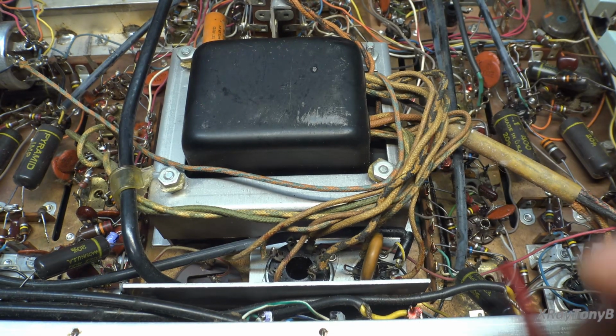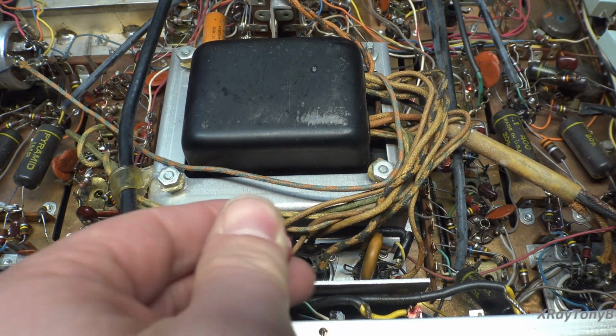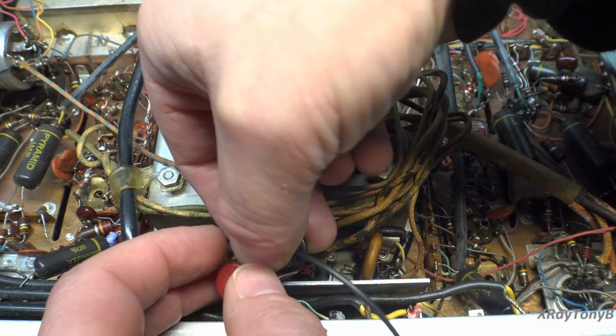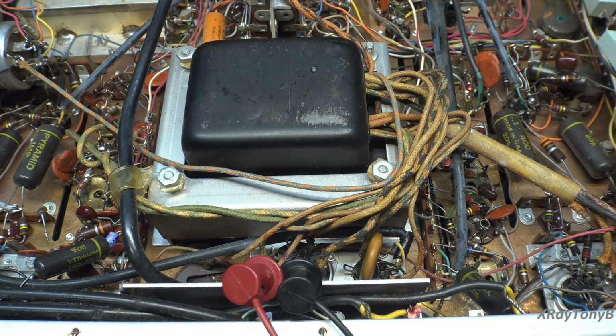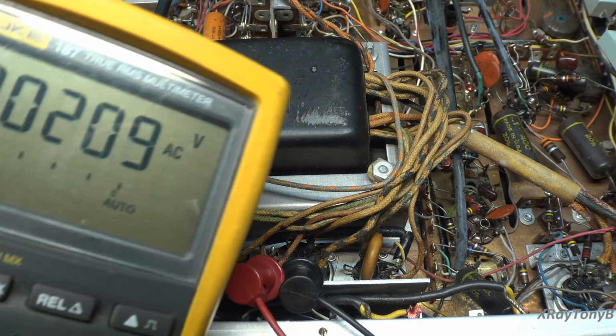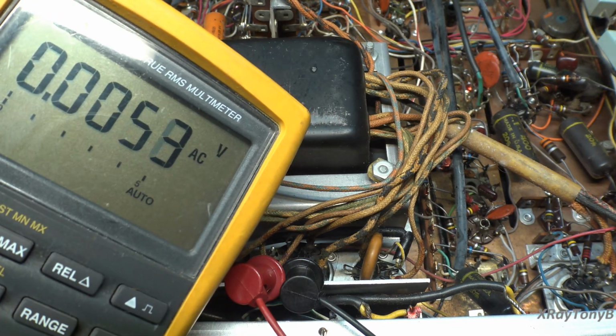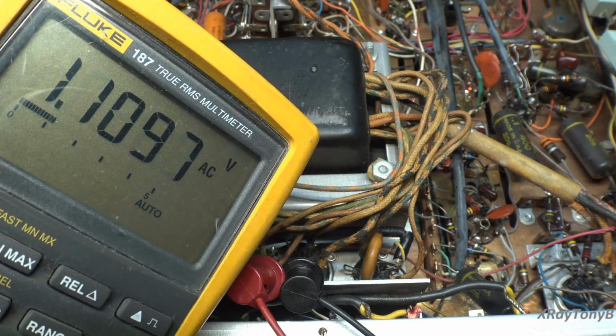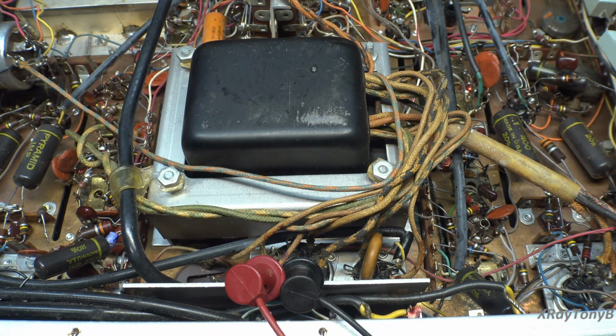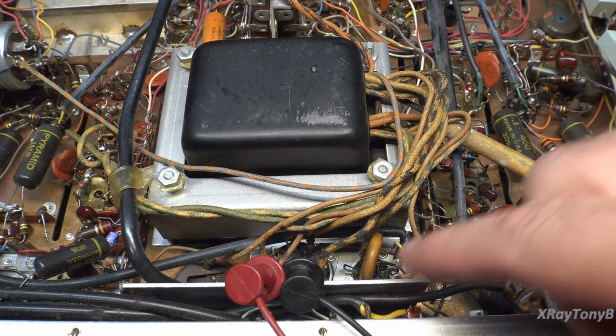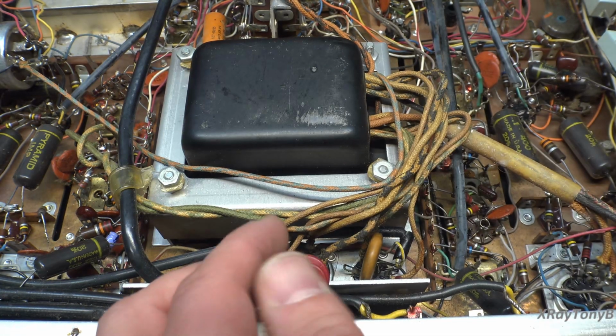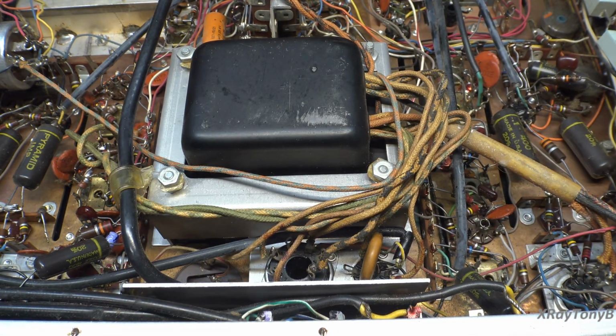With everything disconnected now, we're going to connect back up to this 5-volt winding and see if we get anything there — that might be part of our problem. Let's put this on AC volts, and let's turn it on and see what we get. Only getting about 1 volt. Now that could be because of the short — the light bulb is taking up all the voltage right now, it's all dropping across that bulb. So there's a good possibility that's why the voltage is so low. There's not a short on that winding; we were reading something.